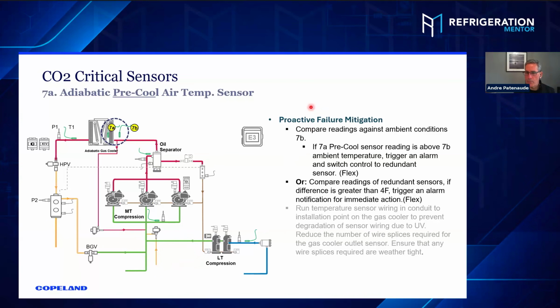So some of the proactive mitigation, you can compare the reading against ambient reading of 7A versus 7B. If 7A, the pre-cool sensor reading, is above 7B, it should not be, trigger an alarm and switch to a redundant sensor. Well, if you have one, but generally you don't, as we mentioned. Other things from a mitigation is compare the reading of a redundant sensor if it's more than 4 degrees. Well, so not a lot of choice there from mitigation if you don't have a redundant sensor.